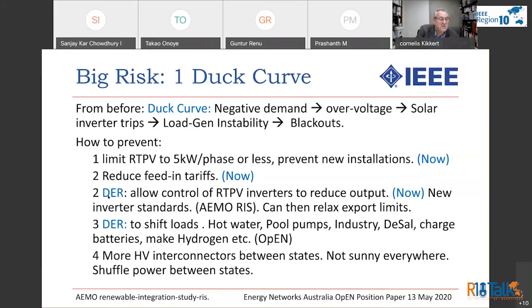The demand control, being able to turn off rooftop inverters to reduce the output, is available now. That's required new inverter standards, and that can then relax export limits so that people can actually export more power when it's needed. You can use demand side management to shift loads, etc. Or we can use extra supply to generate hydrogen, etc. Having more interconnection between states is good because it's not sunny everywhere, and we shuffle power between states.